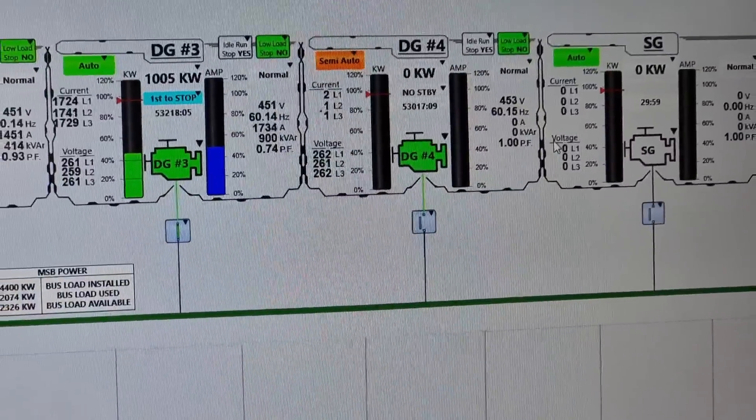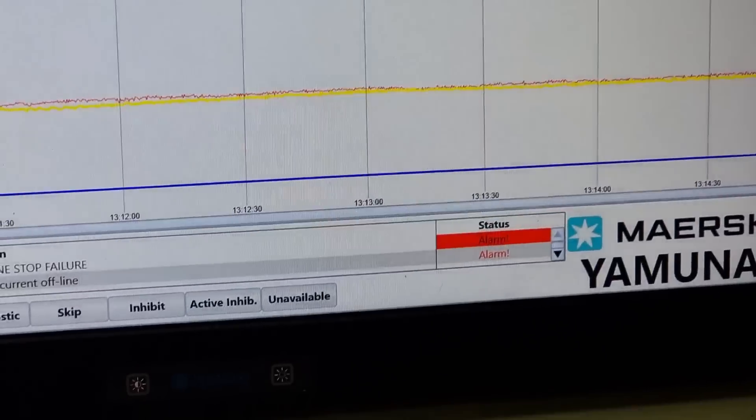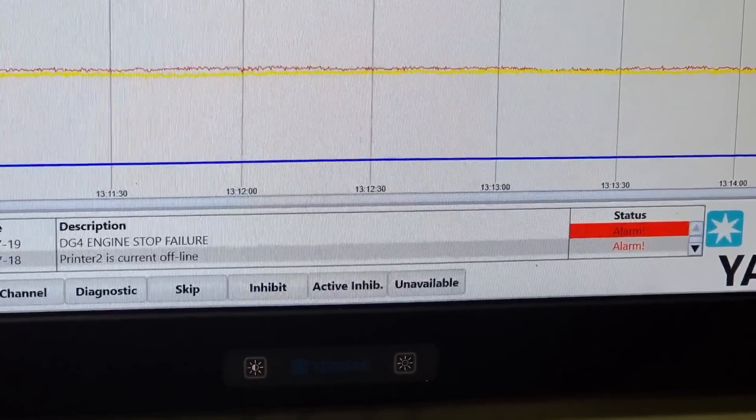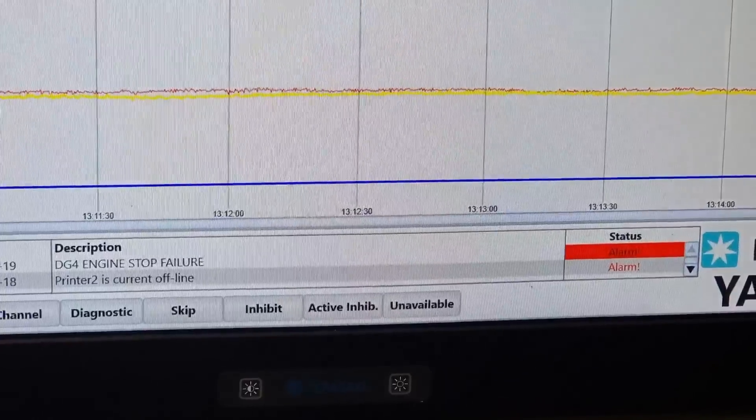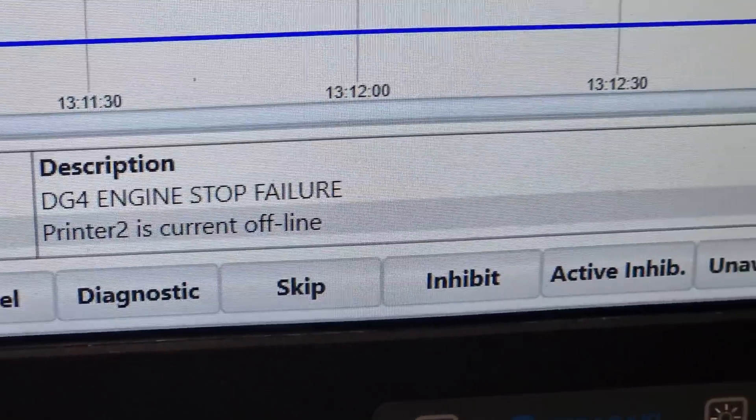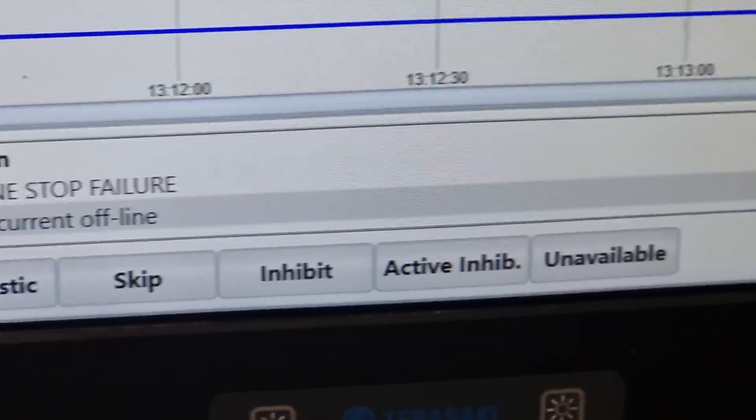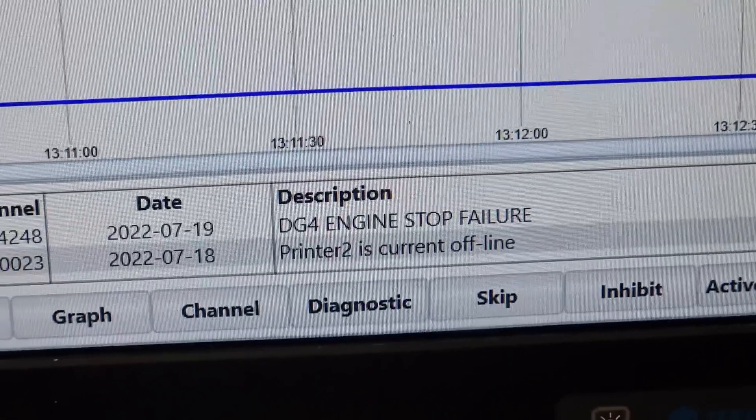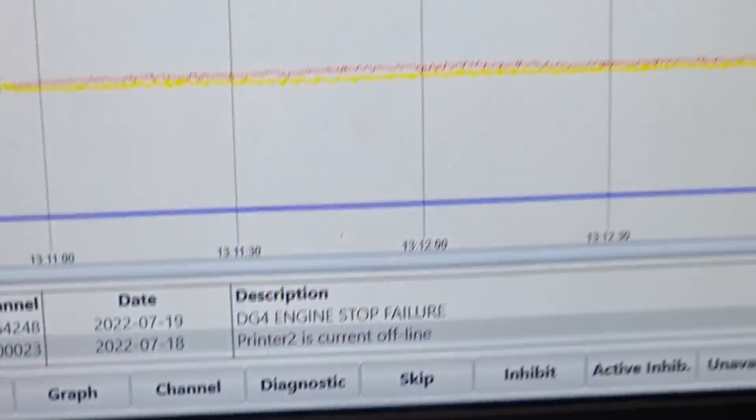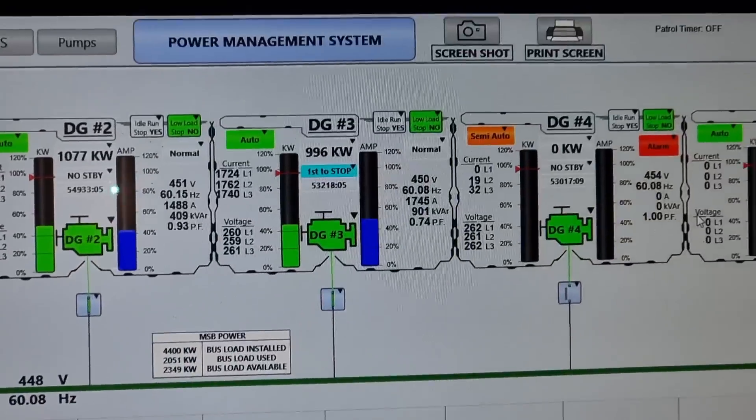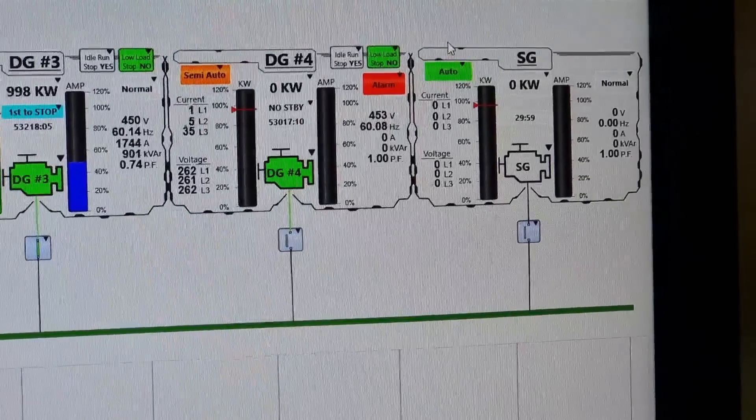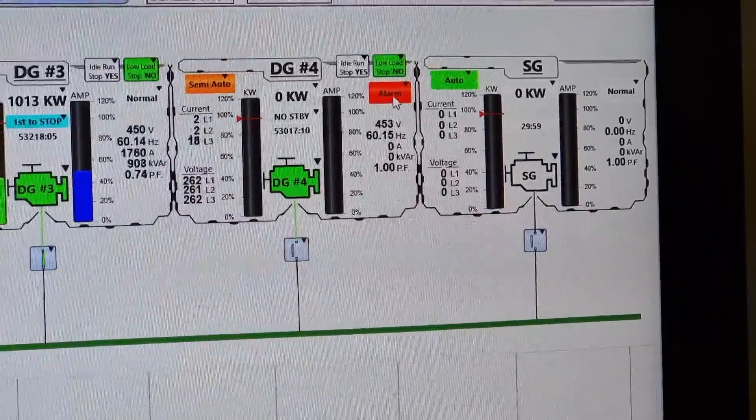Whenever we execute the stop command, we are having this DG 4 engine stop failure in which the generator will not stop and still keeps running in idle operation. So that's what we are going to fix right now.